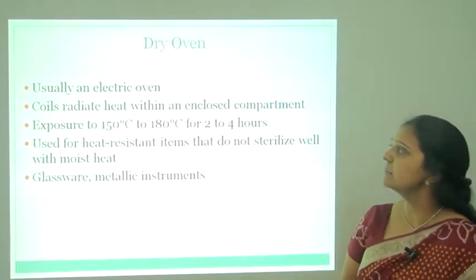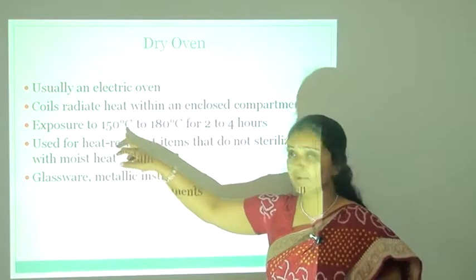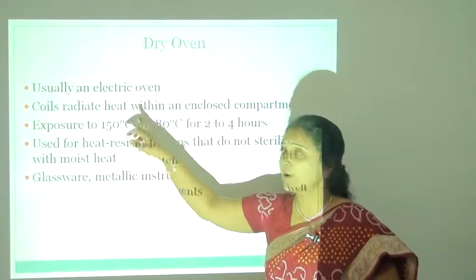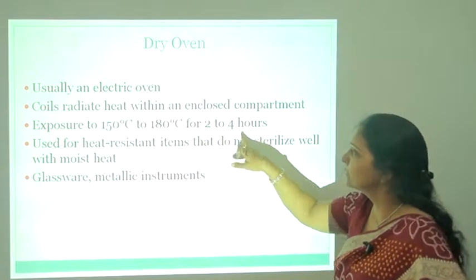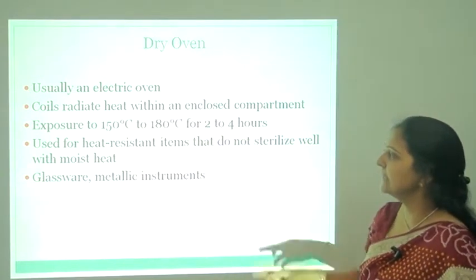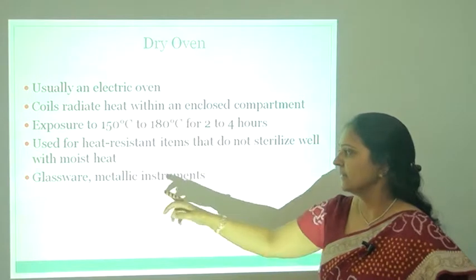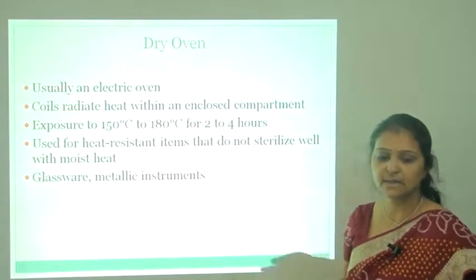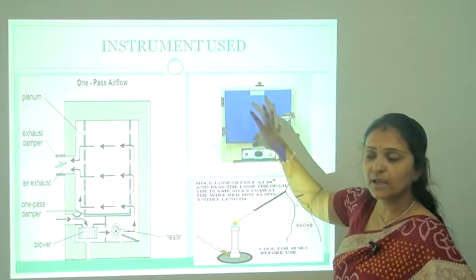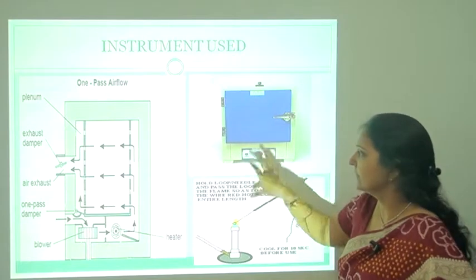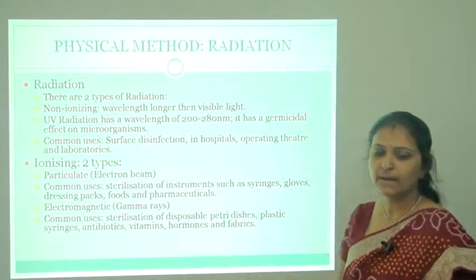The hot air oven is an electric oven. The temperature required for sterilization by hot air oven is 150°C to 180°C for 2 to 4 hours. It is used for sterilization of heat-resistant items such as glassware and metallic instruments. Here you can see the chamber of the hot air oven, which is used for sterilization of glasswares in the laboratory.